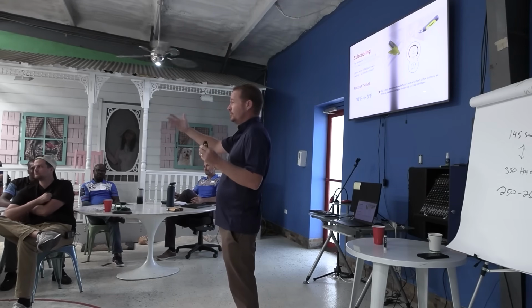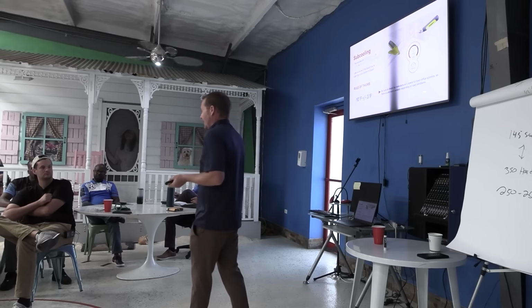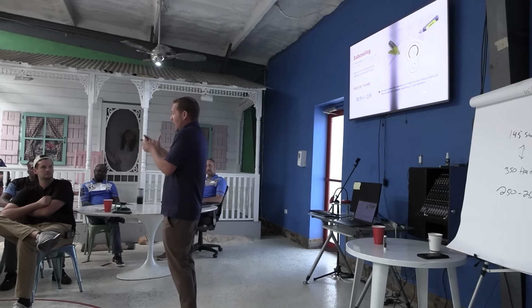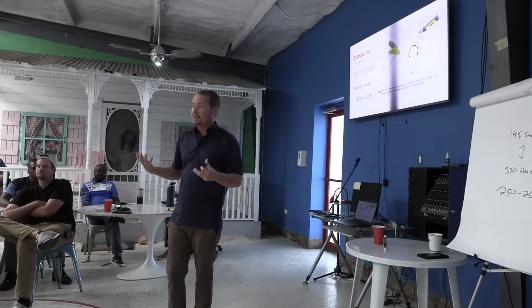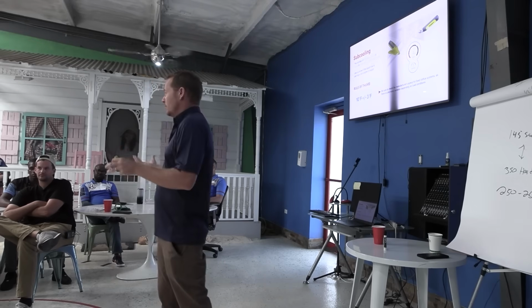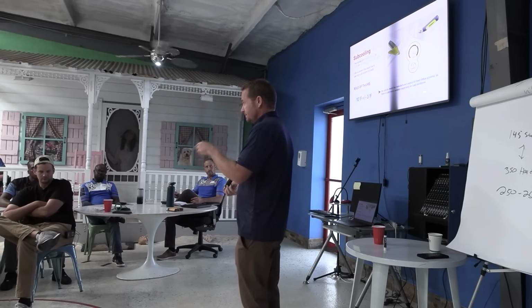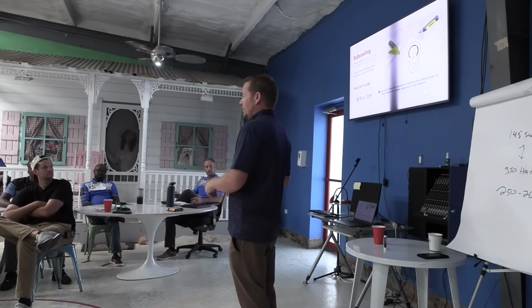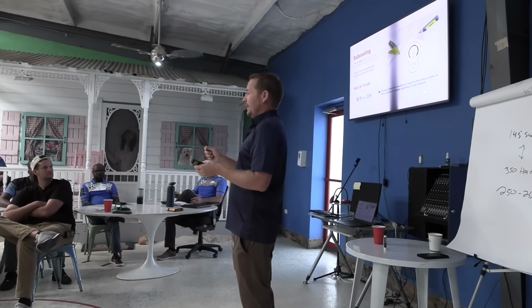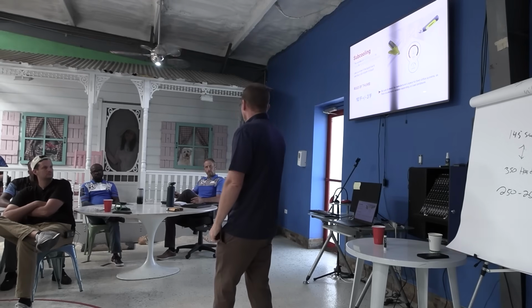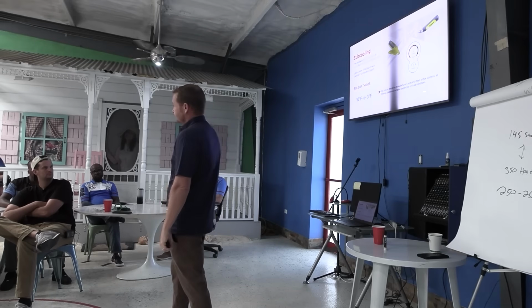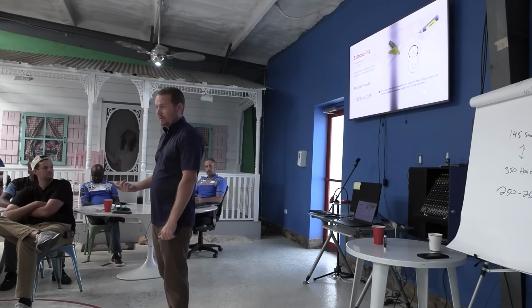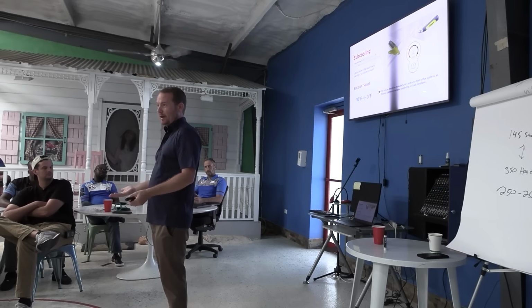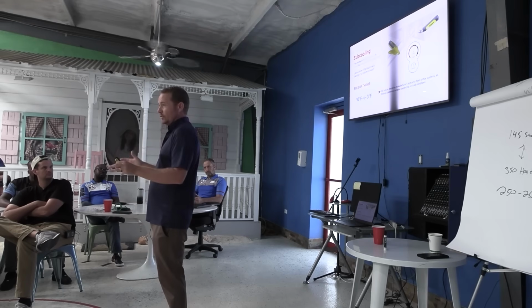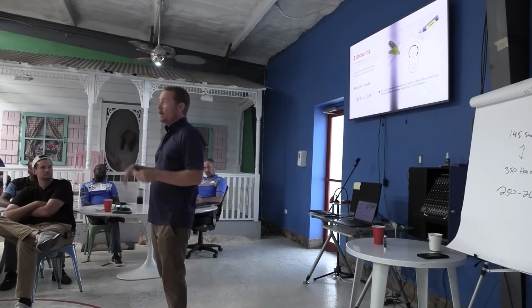Right, exactly. Now, you still check the capacitor, right? You still check that. But that's not what it is. It's an operational overload. And that's a really handy thing to know. And one of the things that drives me crazy is when guys show up and they find a compressor that's out on overload, and they go, oh, hey, I got open windings. Got open windings on the compressor. Well, yeah, you do, because the overload's open, right? That's what the overload does, it opens the windings to common. So, of course you have open windings. Touch it. Oh, yeah, it's hot.